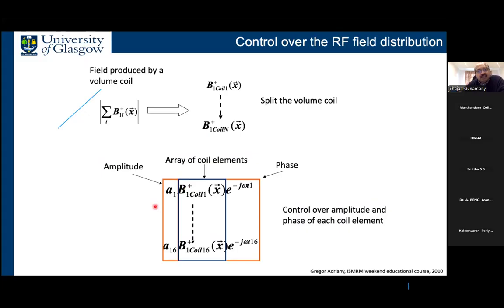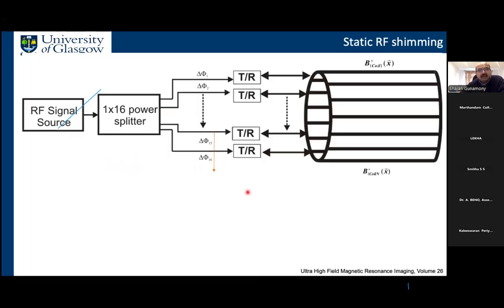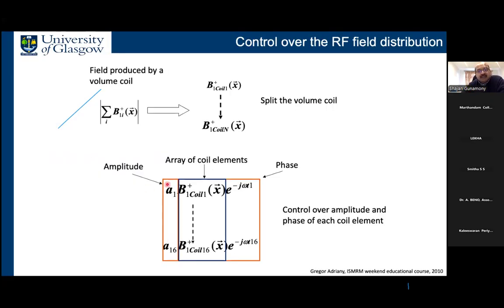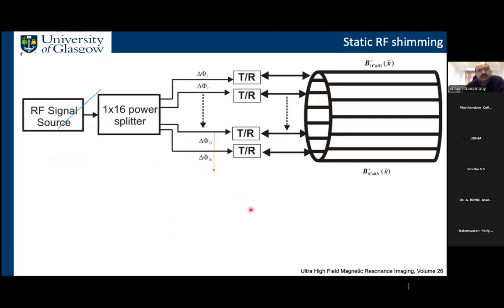Then you can influence the amplitude and phase of the current to each of these coil elements. And that way we can manipulate the field produced by the coil. So what we are doing here is going from a volume coil to an array of coil elements also on the transmit side. When this concept was first introduced, many years ago in the early 2000s, the MRI scanners didn't have multiple RF amplifiers, because for us to do this, we have to have multiple amplifiers. Then on each of these current elements, you can apply different amplitude and phase, and then we can manipulate the field distribution. In those days, this was not available.